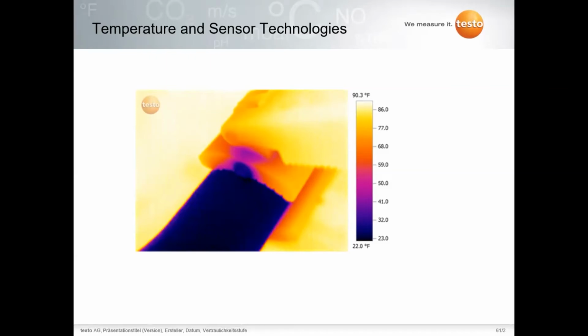But back to the sensor, that yellow or that blue sensor that's in the jaw of the pipe clamp, and it's touching the suction line. That suction line color, dark blue, is the same color as the color of the sensor in the pipe clamp probe. And what that's doing is transferring that measurement into the instrument. So we're really measuring the sensor, the temperature sensor itself, rather than the pipe. There's a transfer of heat again from the suction line to the element or the NTC sensor in that pipe clamp probe.